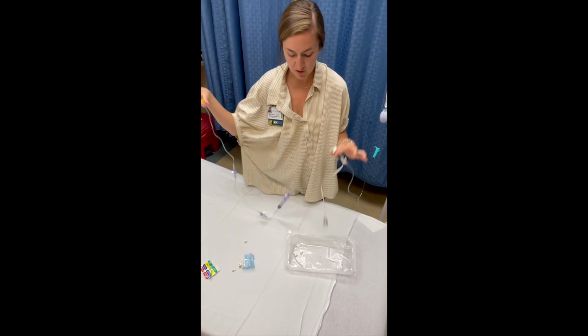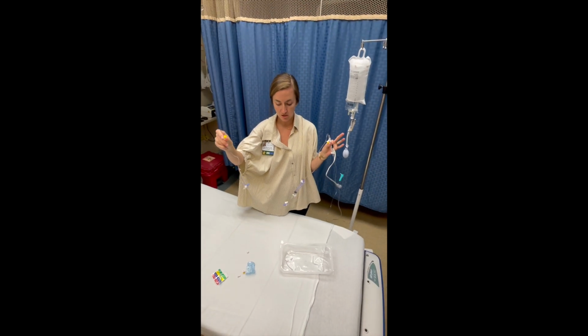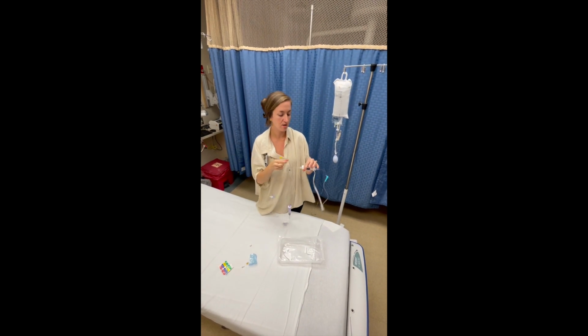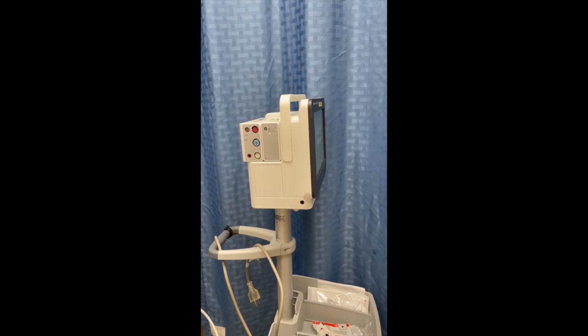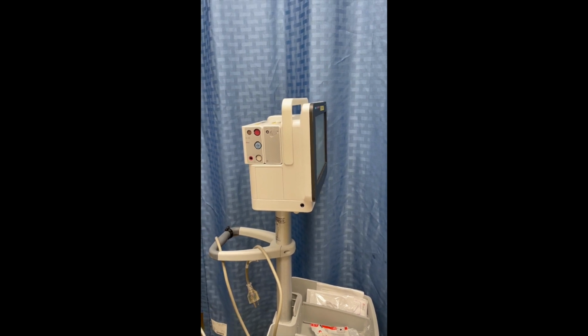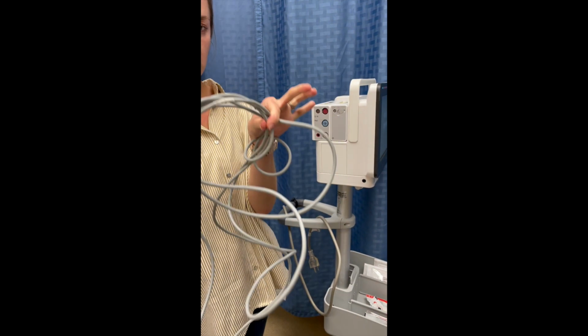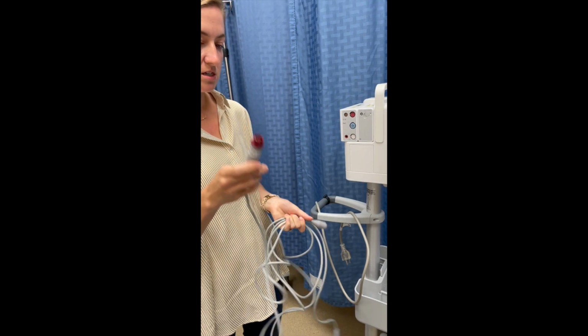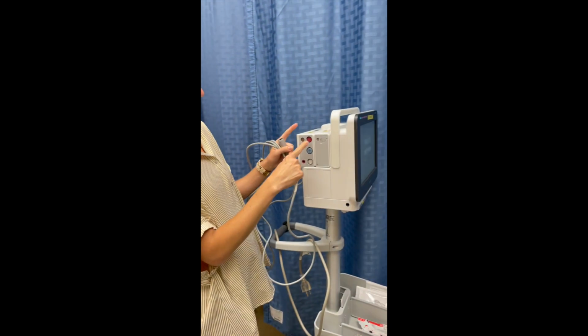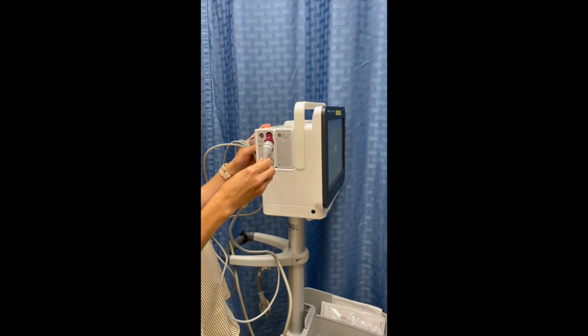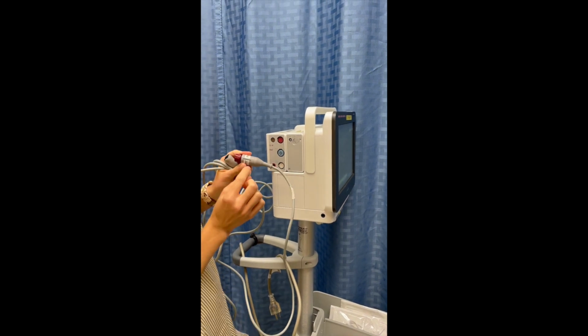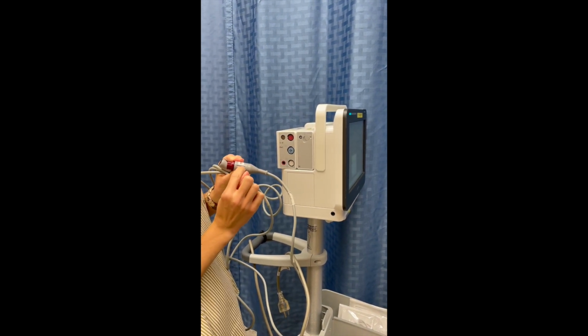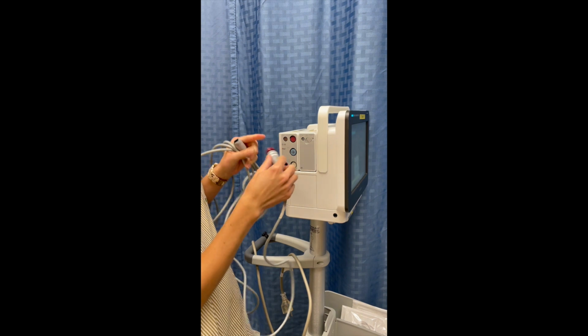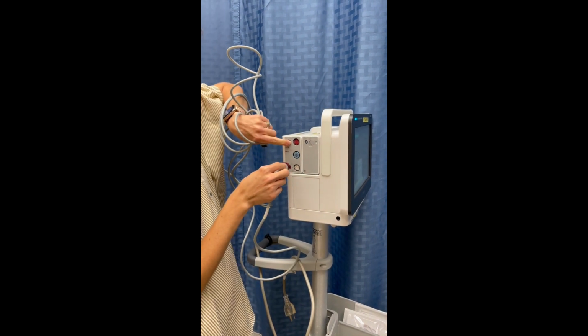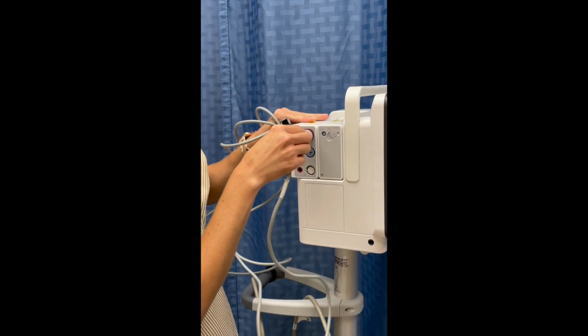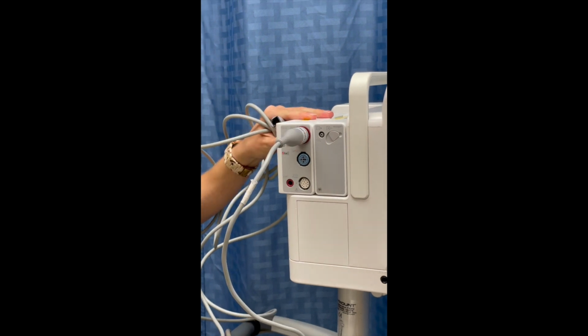And now my system is ready to be attached to the patient once the provider inserts your arterial line. To set up and zero your system, you need to locate the gray cable, which will connect red end to the red pressure port on your monitor. Little tip, there's a raised line here. That's gonna line up with this little dot here. And that makes sure that all of the pins go into the right hole.